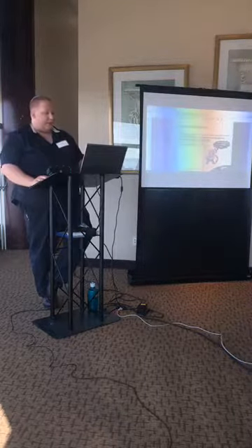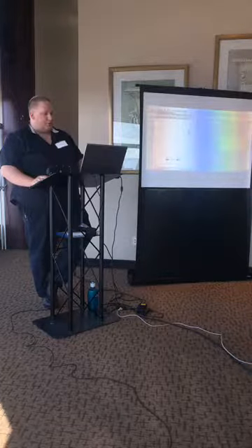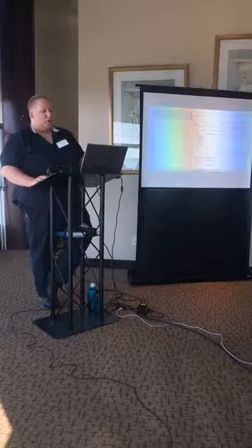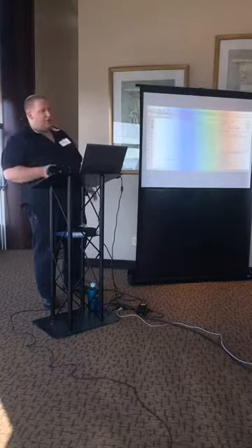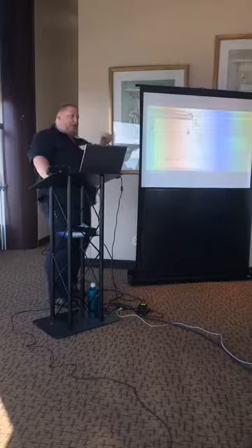Now in Fathom 9, you do have the ability to model submerged pumps, and it's really easy. All you would do is drop a pump on the workspace, and then when you open up the pump, you would use this option to model as a submerged pump, and you would either directly specify the suction pressure at your impeller, or you can specify a pump head or HGL. Now, this is confusing, and so I wrote a blog on this. If you go to our website, aft.com, and under the Learning Center go to Tips and Tricks, I talked about this concept there.